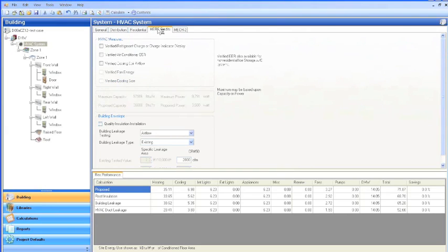And then the HERS credits tab. This is the last tab on the HVAC level. On here, you're going to enter in the infiltration levels that you obtained through your blower door testing. Your CFM 50 number goes here on the existing. So if you make sure this says airflow and existing, you put the number in here. If you are, and this may happen if you're using a HERS rating or rater to get the information, you may be getting specific leakage area. You can pick that, and then you would be able to enter in the SLA over here.